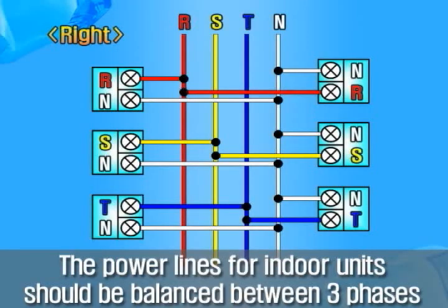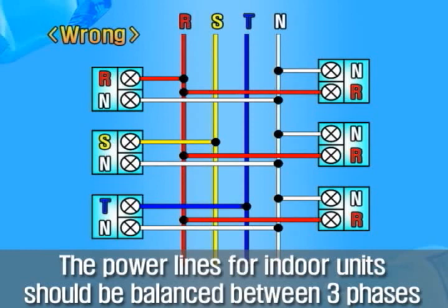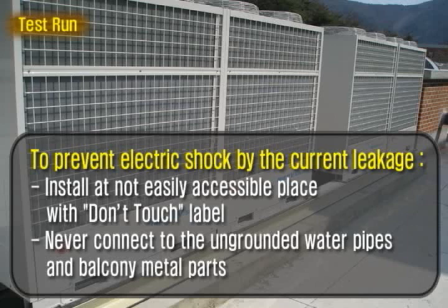For more than 2 units of outdoor units, the cable connection of indoor units to circuit breaker should be balanced in loads to each R, S, and T phase. The main circuit breaker will operate when they're not balanced. In case the power line is not grounded, request the customer to get the grounding done by calling the local electric company.